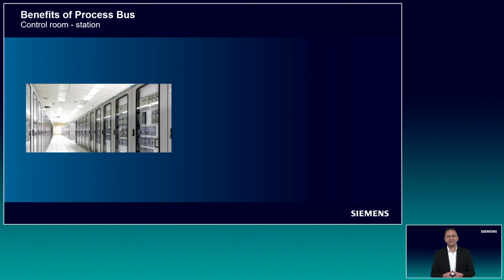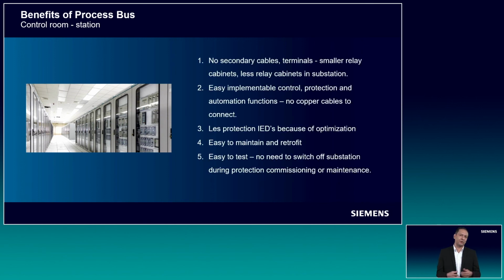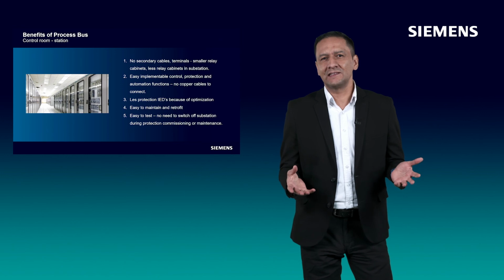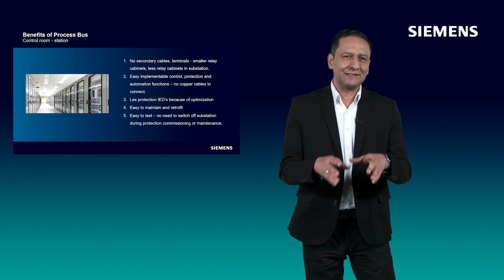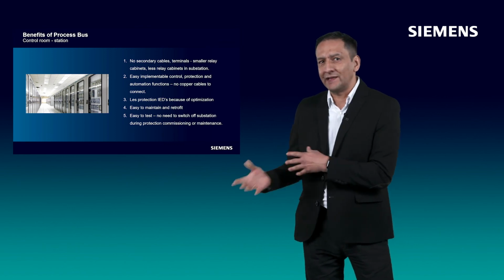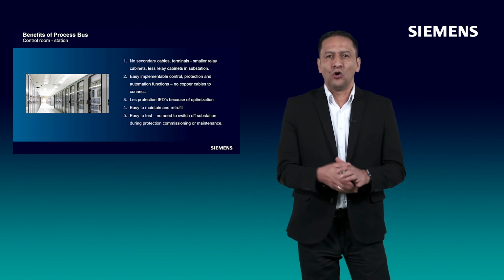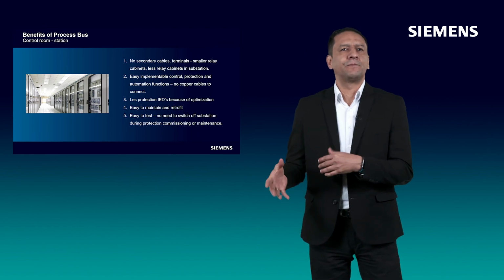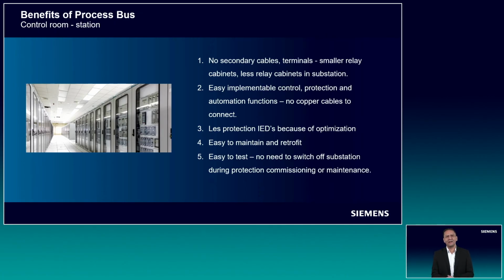Speaking about the control room, we have a much smaller amount of relay cabinets than before, because multiple protection and automation functions can be implemented in one protection relay. Also, there are no terminals and copper cables like before. Relays can be smaller as they have no binary inputs, binary outputs or analog inputs. Also, signals from the field are transmitted via fiber optic cables. So it's easier to commission and maintain such a substation. Especially, it will be very easy to retrofit substations as we will use only merging units, fiber optic cables, and protection devices with switches.